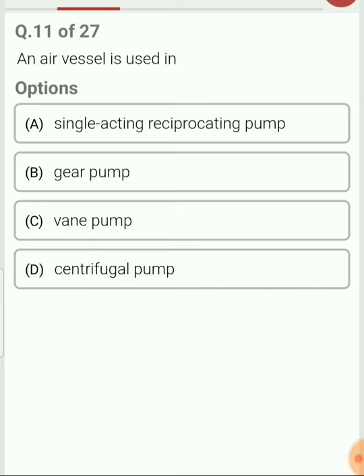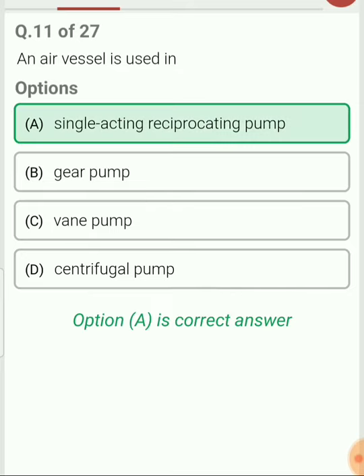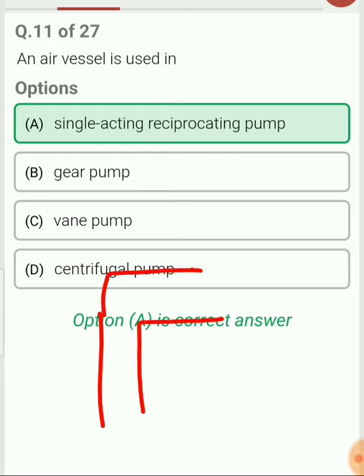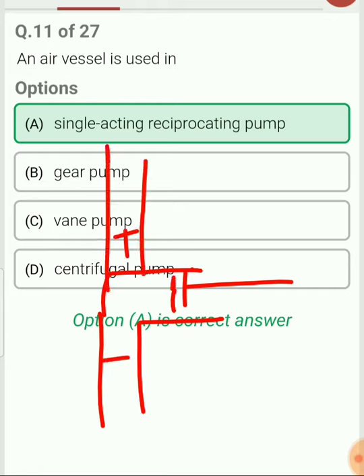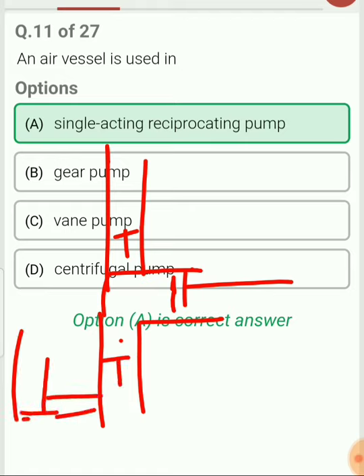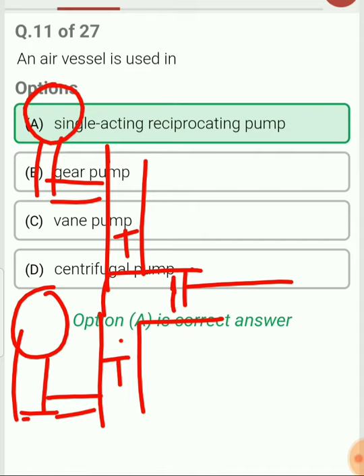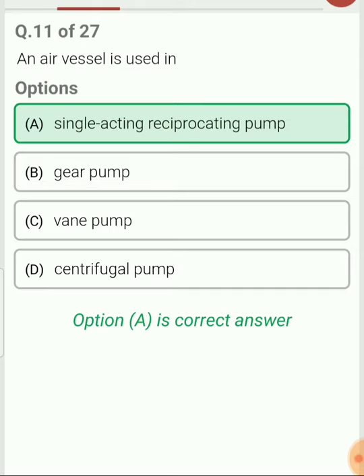Air vessel is used in a single acting reciprocating pump. There is a suction pipe, a cylinder, a piston that reciprocates inside the cylinder, and a delivery pipe. Towards the suction pipe and delivery pipe there is an air vessel. The function of the air vessel is to maintain continuous flow — with the help of an air vessel we can obtain continuous delivery of water in the single acting reciprocating pump.